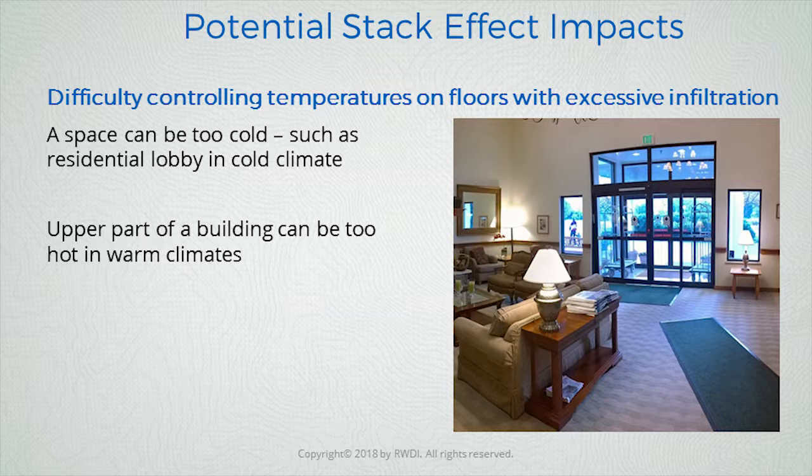And an example I'll give to you is I was at the top of a tall building in Dubai. There was a gymnasium up there as well as a pool deck. And as people were going out to the pool deck, there was a surge of warm air that was coming in, raising the temperature inside the gymnasium, which then made it difficult for the athletes to exercise. And by the time the air conditioning system had caught up and made it cool again, someone else came in or out of that pool deck. So there's an example where that can affect building occupants directly.